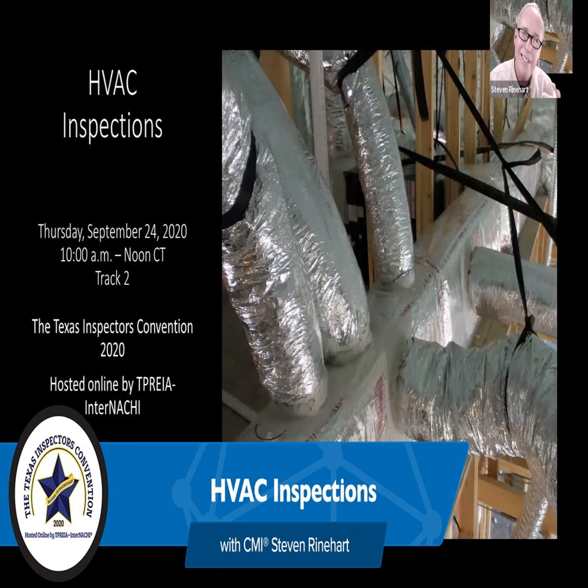Okay. Presence of gas piping. I've only found one HVAC plenum that actually had a 3-inch sewer pipe going right through the middle of it. Kind of rare. I think they put that in there just to say, if you ever saw a plenum, and it wouldn't be a flex duct, but if you saw a plenum with any kind of sewer gas piping going through it, it's a defect.